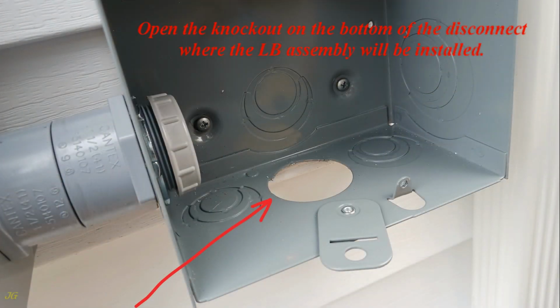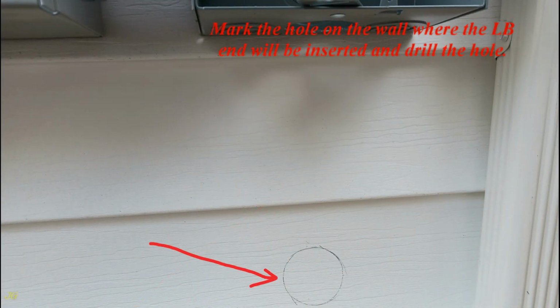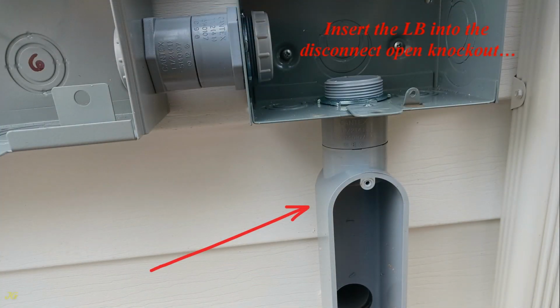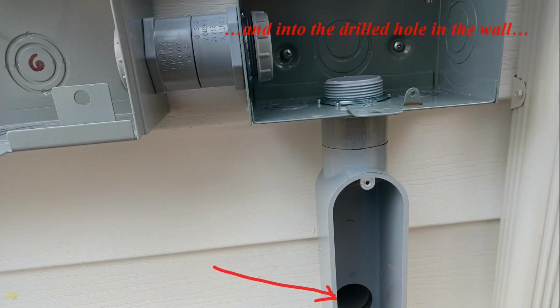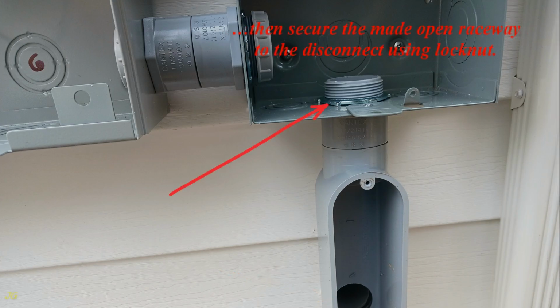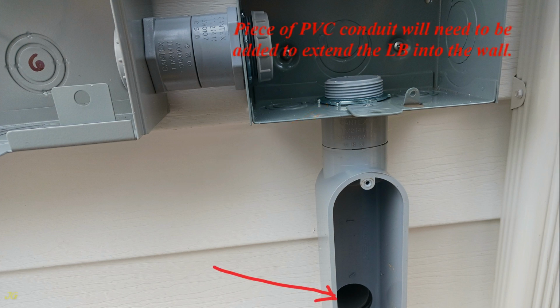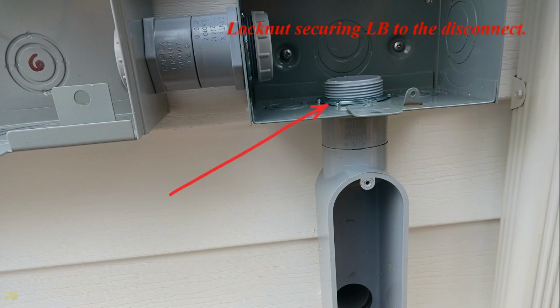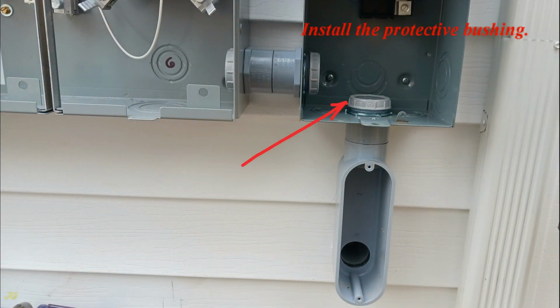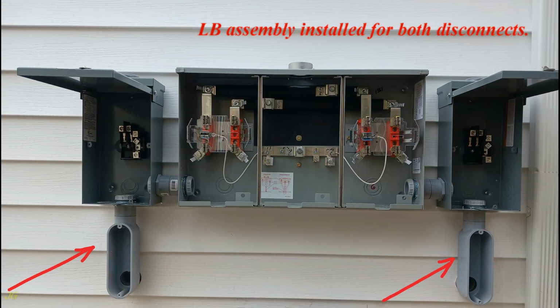Open the knockout on the bottom of the disconnect where the LB assembly will be installed. Mark the hole on the wall where the LB end will be inserted and drill the hole. Insert the LB into the disconnect open knockout and into the drilled hole in the wall. Then secure the made open raceway to the disconnect using lock nut. A piece of PVC conduit will need to be added to extend the LB into the wall. Lock nut securing LB to the disconnect. Install the protective bushing. LB assembly installed for both disconnects.